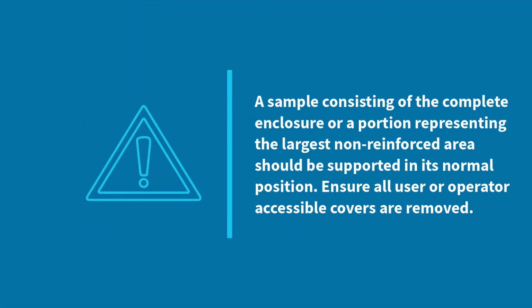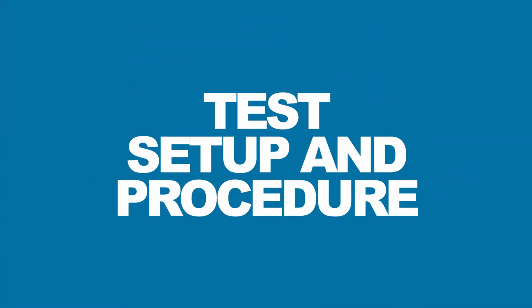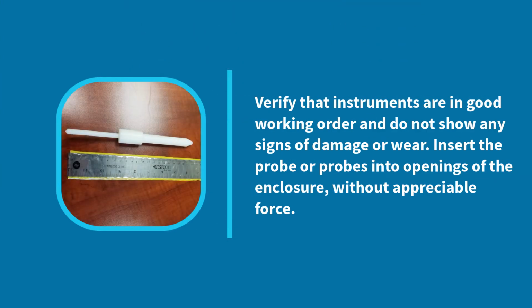Probe test. A sample consisting of the complete enclosure or a portion representing the largest non-reinforced area should be supported in its normal position. Ensure all user or operator accessible covers are removed. Test setup and procedure. Verify that the instruments are in good working order and do not show any signs of damage or wear. Insert the probe or probes into openings of the enclosure without appreciable force.